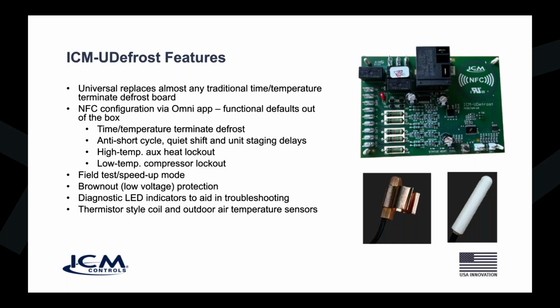We also have a field test mode for technicians to test the device in the field. It detects low voltage or brownout conditions, has a diagnostic LED indicator to give you diagnostic fault codes to aid in troubleshooting when something goes wrong. And it has a thermistor style sensor, coil sensor, and outdoor air temperature sensor provided with the product.